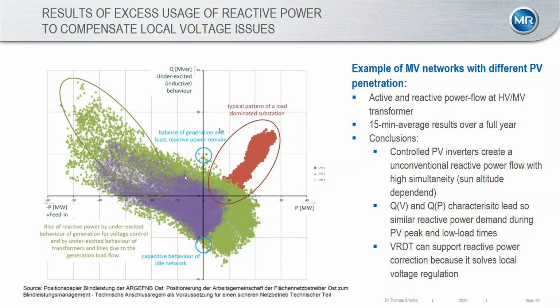But also take care about your usage of inverters in the future. As we all know, the spinning reserve and synchronous generators will be disconnected in the next 20, 30 years. So we will have an electricity system with much more power electronics and inverters, and different technologies will have to solve the same issues we see today, like voltage control, reactive power flow, and frequency stability to keep the system alive.